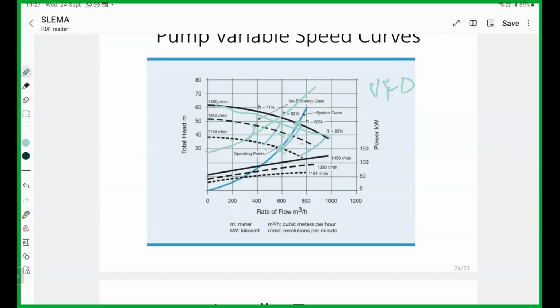You can see here that the pump efficiency is somewhere here, right? 83. If you reduce the speed, your pump efficiency may decrease. The duty point is somewhere here. These are iso-efficiency curves, right? Ideally, the VFD application is good for a closed system, right? If the system curve is flat, generally the VFD application is not accepted, right?